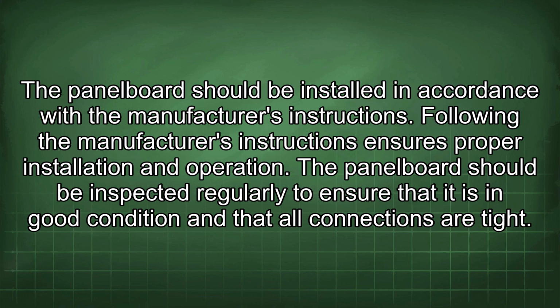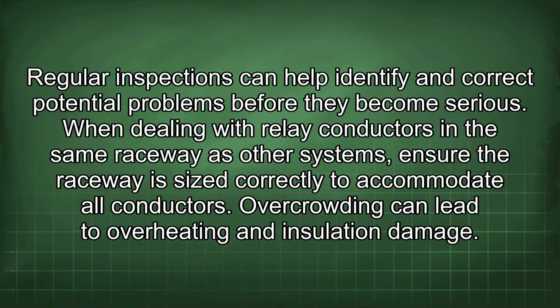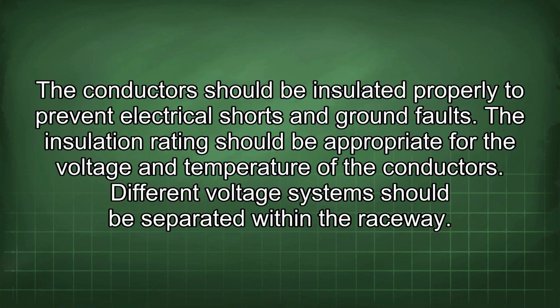The panel board should be inspected regularly to ensure that it is in good condition and that all connections are tight. Regular inspections can help identify and correct potential problems before they become serious. When dealing with relay conductors in the same raceway as other systems, ensure the raceway is sized correctly to accommodate all conductors. Overcrowding can lead to overheating and insulation damage. The conductors should be insulated properly to prevent electrical shorts and ground faults.